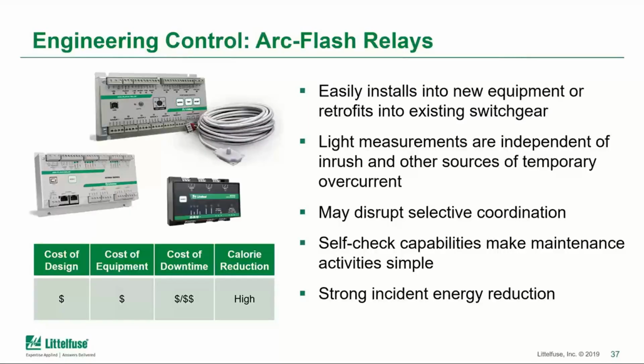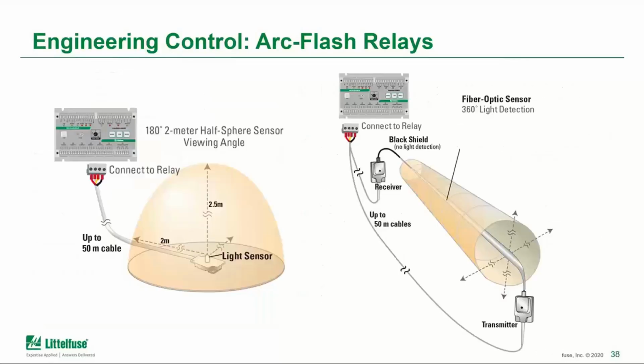The cost of the downtime is usually on the lower side. Most installations don't take too long to layer in, but if you have more significant or more dense equipment with components, there is a possibility of taking a little bit longer to do that install. So I have shown it as a low to medium cost for downtime. The arc flash relays do provide a very strong calorie reduction in terms of mitigation, so I show that as a high calorie reduction as well.